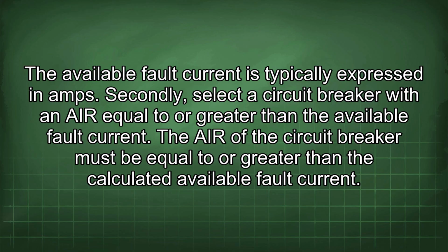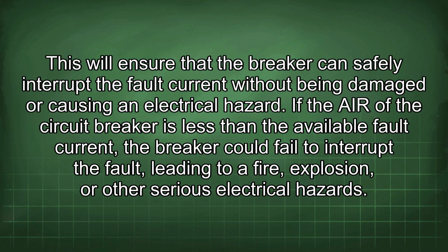Secondly, select a circuit breaker with an AIR equal to or greater than the available fault current. The AIR of the circuit breaker must be equal to or greater than the calculated available fault current. This will ensure that the breaker can safely interrupt the fault current without being damaged or causing an electrical hazard. If the AIR of the circuit breaker is less than the available fault current, the breaker could fail to interrupt the fault, leading to a fire, explosion, or other serious electrical hazards.